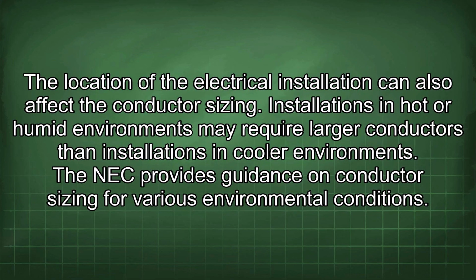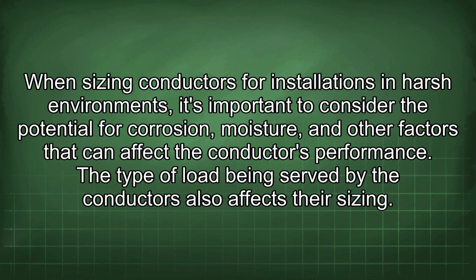The location of the electrical installation can also affect the conductor sizing. Installations in hot or humid environments may require larger conductors than installations in cooler environments. The NEC provides guidance on conductor sizing for various environmental conditions. When sizing conductors for installations in harsh environments, it's important to consider the potential for corrosion, moisture, and other factors that could affect the conductor's performance.